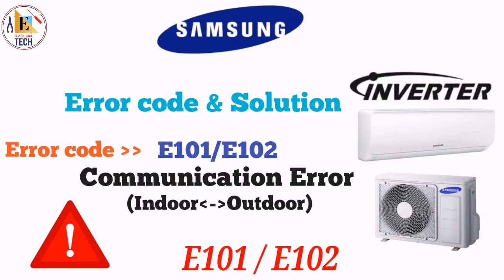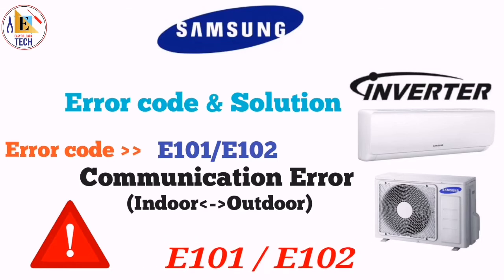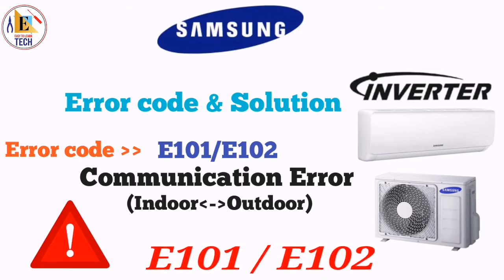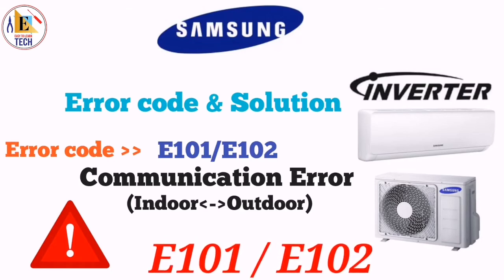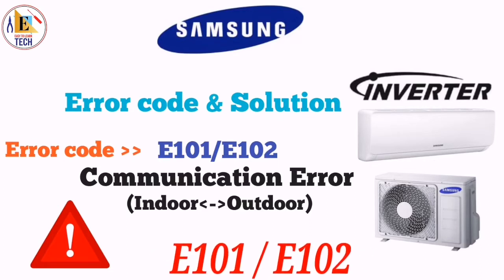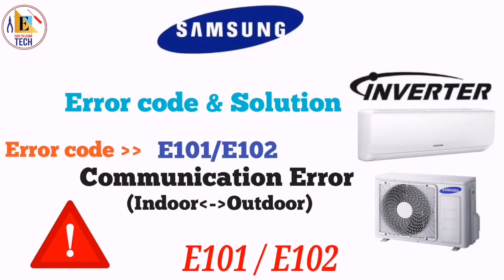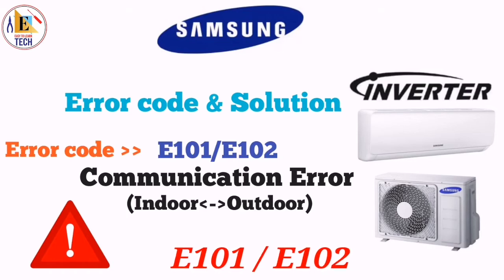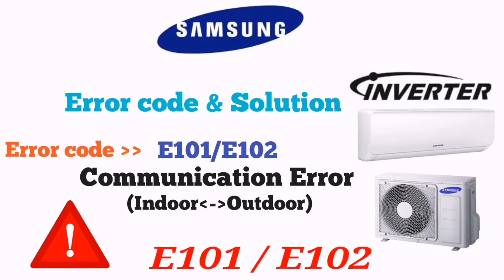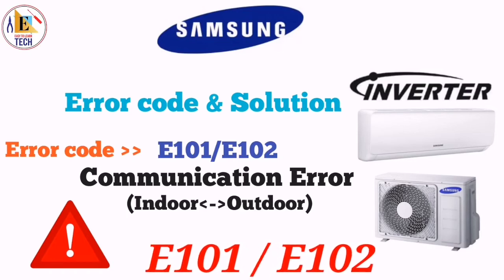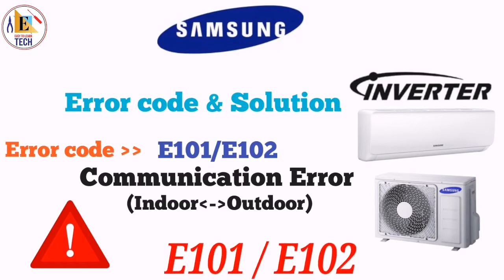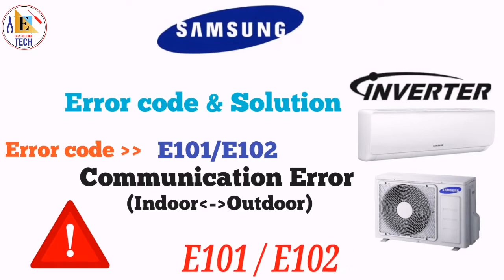If your power cable and communication cable are connected properly, then you have to exchange your PCB. After exchanging the PCB, just give the power again. Then check whether communication is okay or not. If your communication is okay, it means the fault was the indoor PCB. Even if you change the PCB and it's still not okay, then you have to change your outdoor PCB and your system will be working.